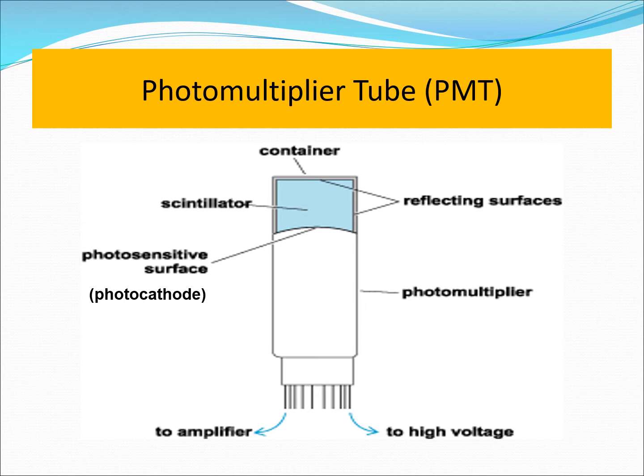If this scintillation device is used for technetium-99m measurement, then the scintillator material is commonly sodium iodide activated by thallium. But for higher energy photons, like in positron emission tomography, the PM tube will be using a different scintillator crystal material.